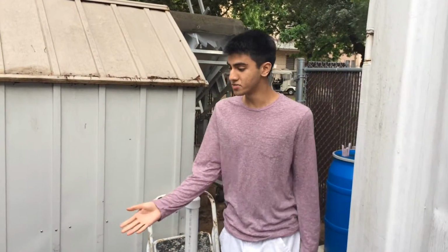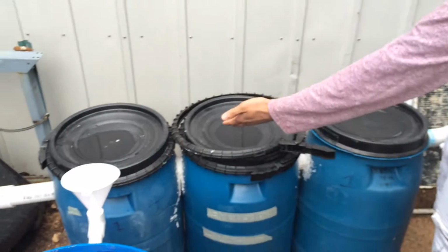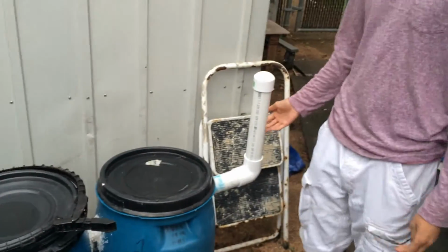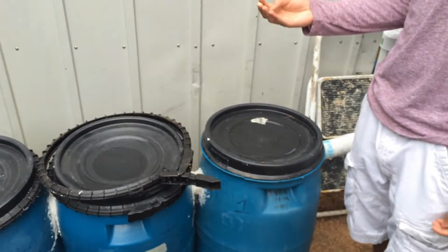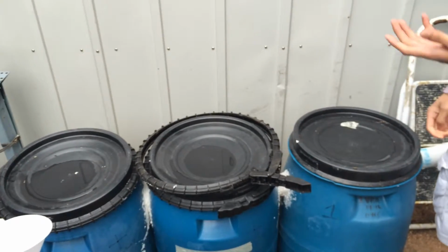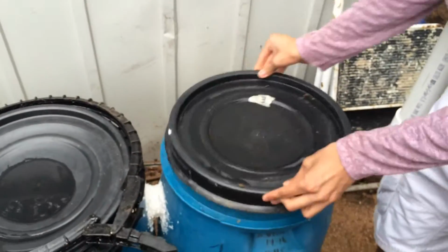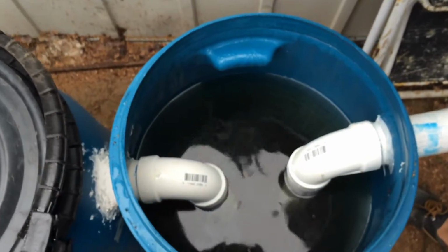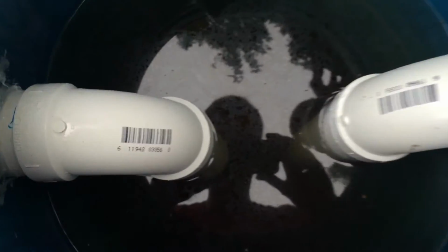Here, we're going to demonstrate our anaerobic baffled reactor as shown in these 3 separate tanks connected by PVC pipe. As water flows in through the inlet pipe, it'll flow into the first tank, where particulate matter in the water will settle as water sits in this tank. As that particulate matter settles, as you can see here, the bacterial culture will start to form at the bottom where this particulate matter sludge exists.